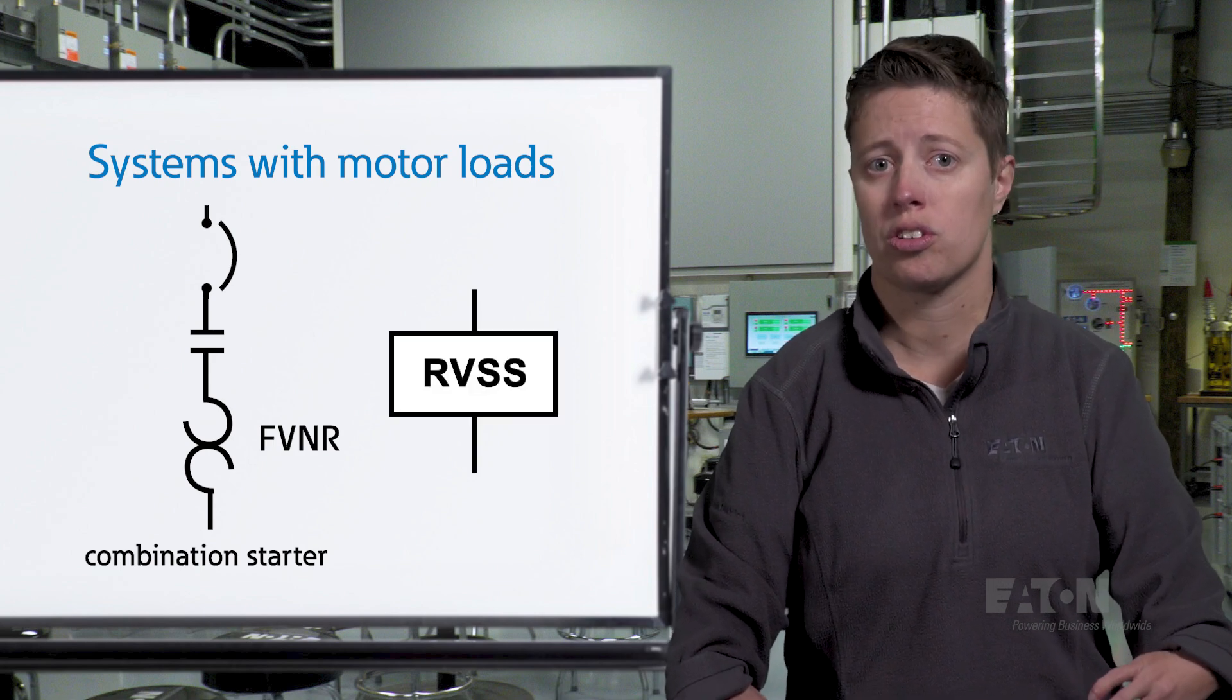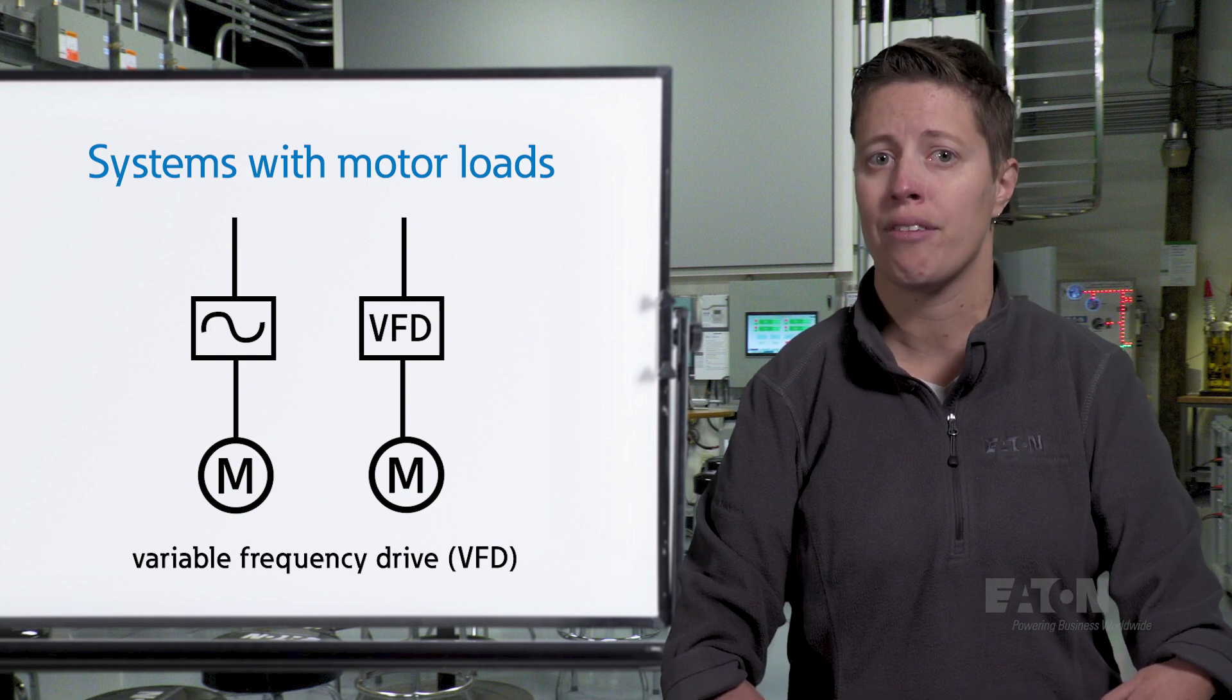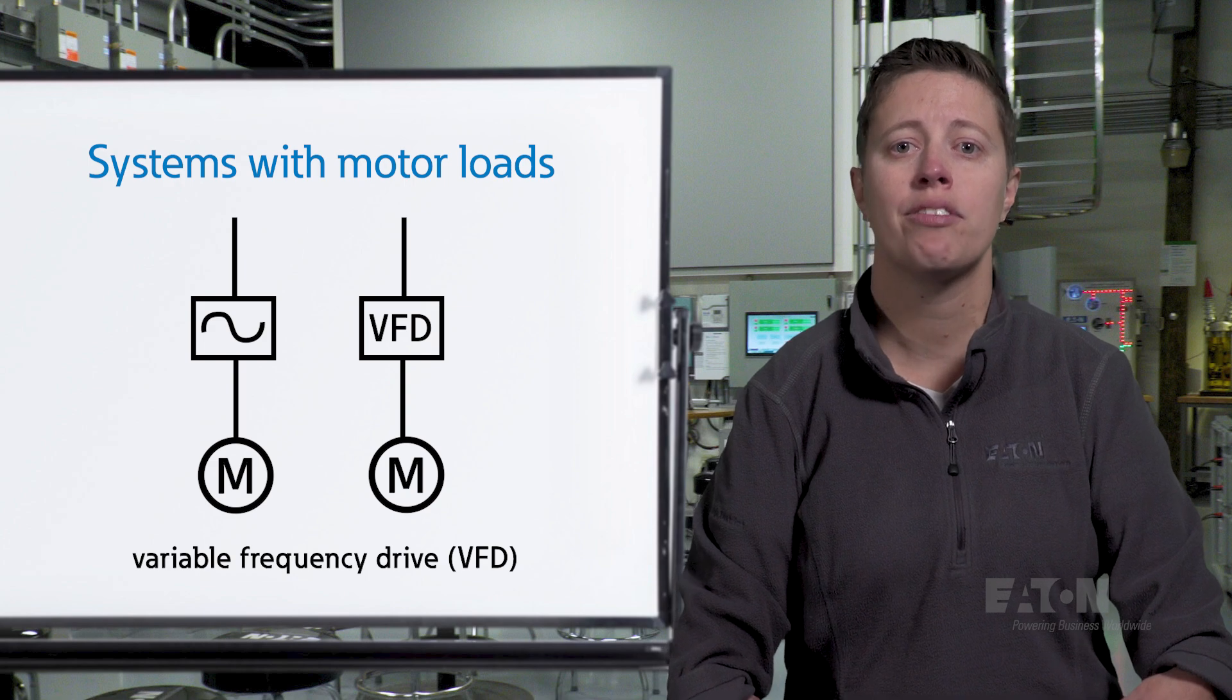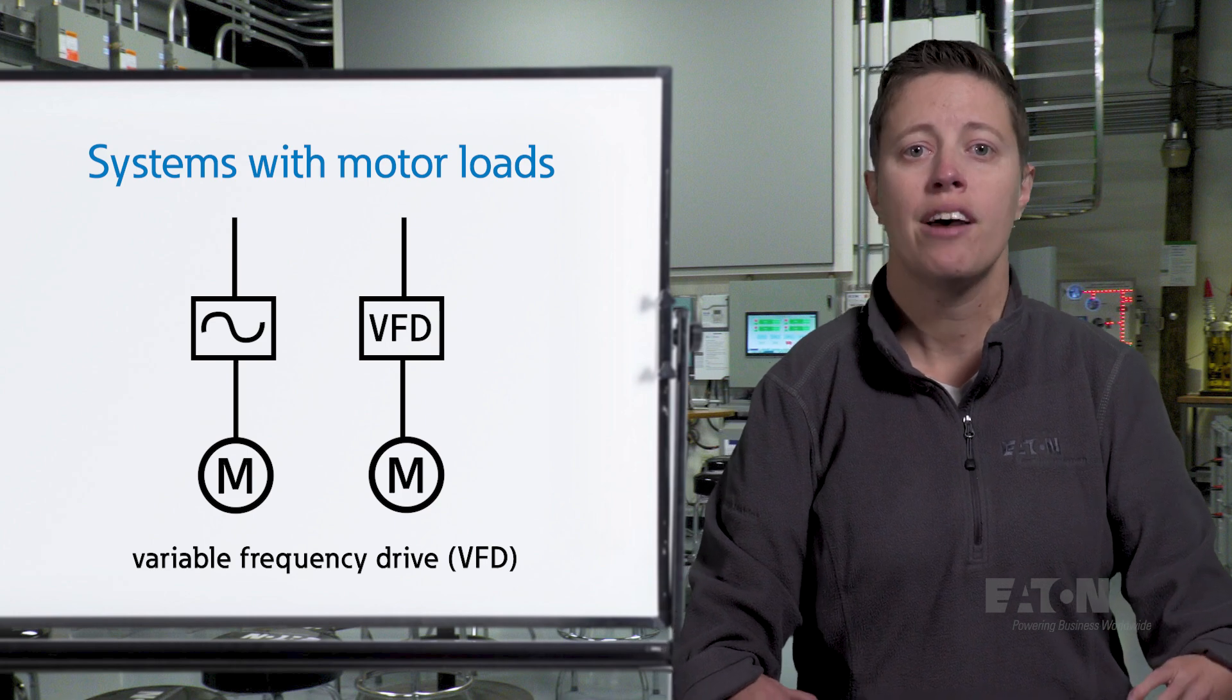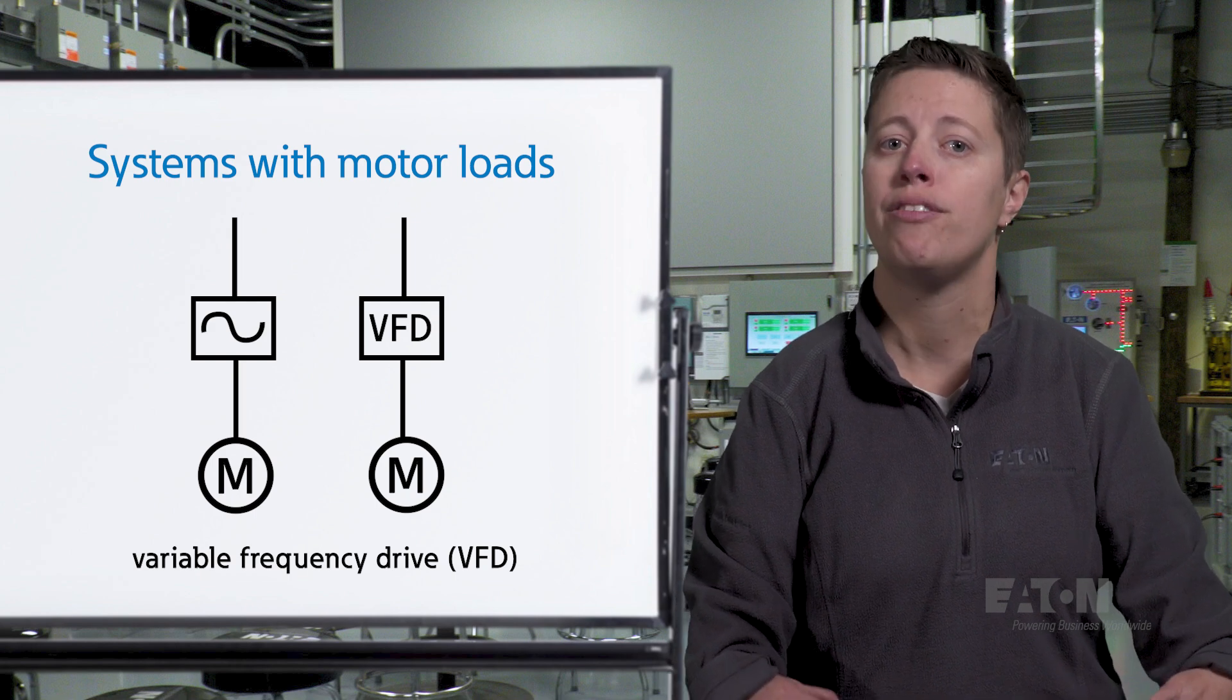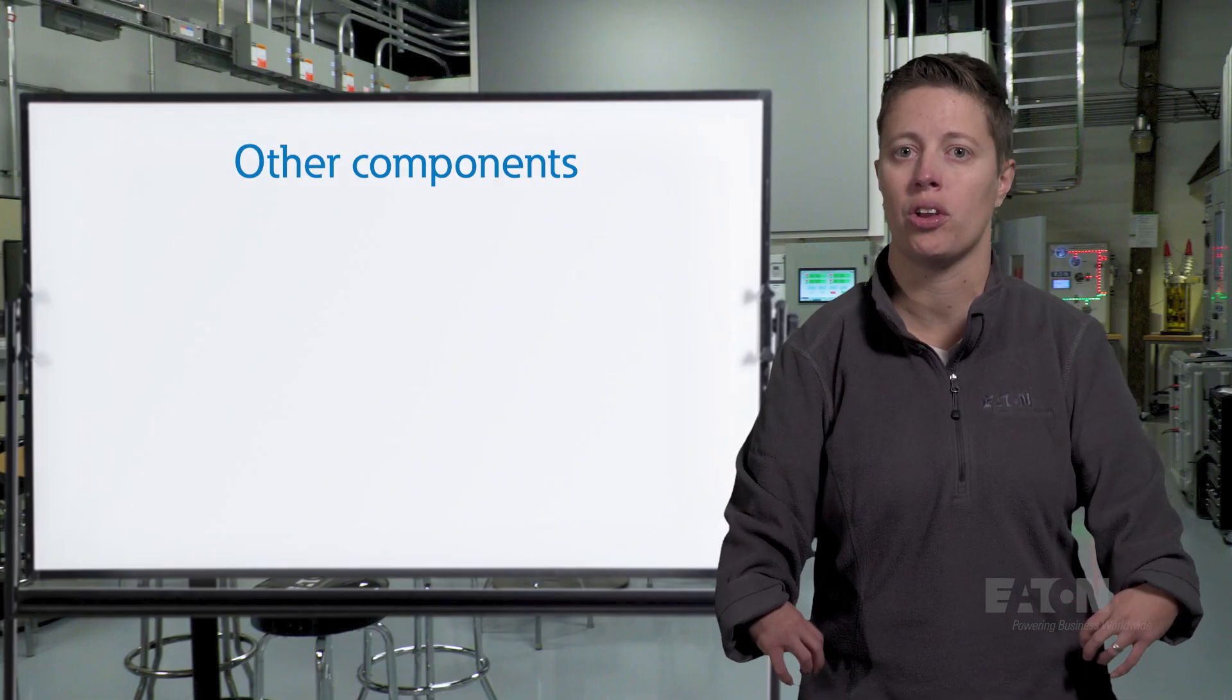For reduced voltage starting, you may see the abbreviation RVSS. You may also find a variable frequency drive, or VFD, on the single line. This symbol is often a rectangle with a wave symbol inside, or the letters VFD. A VFD is a device that controls the speed and torque of an electric motor by varying the frequency and voltage of its power supply. There are also some additional components we should be on the lookout for.